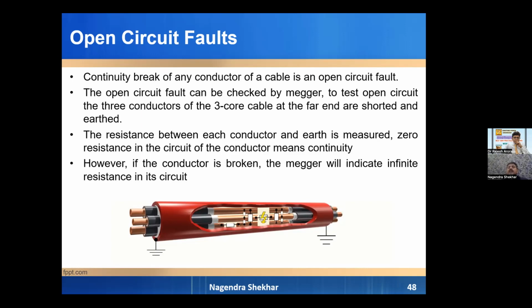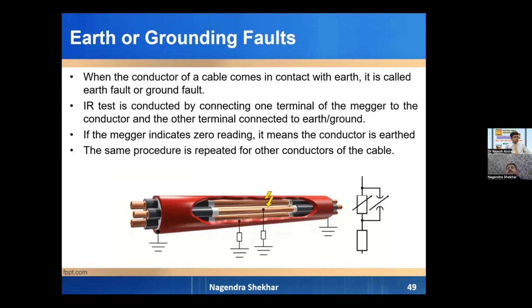Later on, digging was redone and we found that at a distance of 4-5 meters there was a heat shrink joint. While the cable was being damaged by the JCB, it was stretched and the ferrules were loosened, though it was maintaining a proper distance. There was no short circuit, nothing was there. The IR test was conducted and it was good and the cable was energized, but due to the open circuit the supply did not reach the second portion. Then the earth or ground fault is when the phase is grounded with the earth. Usually such faults occur with short circuit faults.